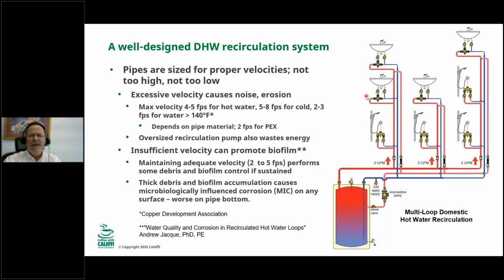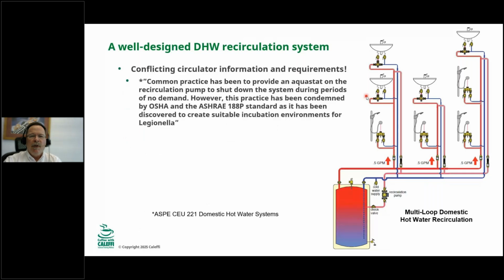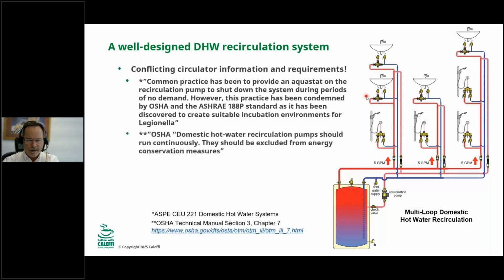Okay, now this is a controversial subject: circulators. You can see in this bullet here that according to this ASPE CEU document, we should run the circulator all the time. And you can see that quote there that OSHA and ASHRAE 188 mention it. There's the OSHA reference saying that the circulator should be excluded from energy conservation measures in favor of keeping the water moving.